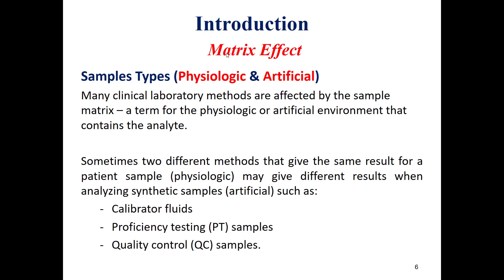Now we'll talk about the matrix effect — the difference between a patient sample, which is considered a physiological or natural sample, and a synthetic or artificial sample such as a calibrator, quality control, or proficiency testing. Many clinical laboratory methods are affected by the sample matrix, a term for the physiological or artificial environment that contains the analyte.